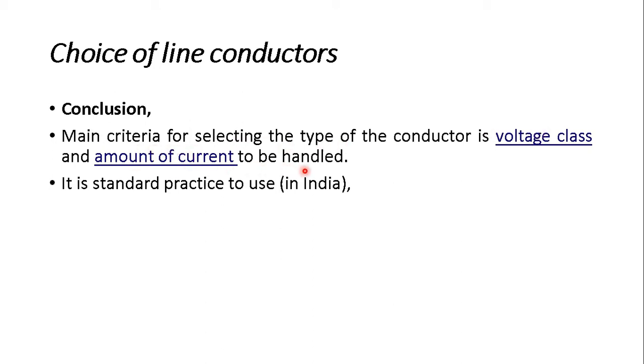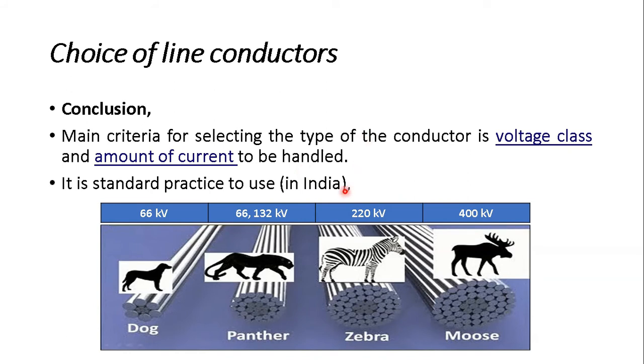In India, standard practice uses the following conductors for different voltage levels: for 66 kV, ACSR Dog conductor is used; for 66 kV or 132 kV, ACSR Panther conductors are used; for 220 kV, ACSR Zebra conductors are used; and for 400 kV, ACSR twin bundle Moose conductors are used. Based on the voltage level and amount of current to flow, we select the appropriate conductor.